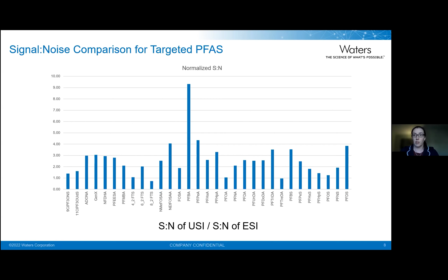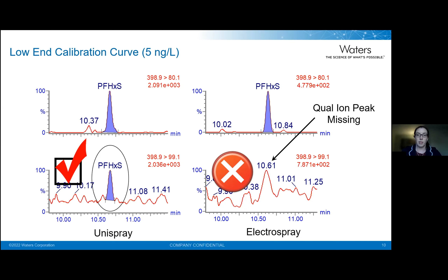So looking at this calibration point for perfluorohexane sulfonate, the Unispray chromatograms are on the left, electrospray is on the right. The top transition is our quantification ion, and the bottom is our qualifier. Usually for us to say that this compound is detected, we need to see traces in both. You can see with the electrospray, we're missing that qualification ion. That qual ion peak is missing, but we do see it in Unispray. So we could call this bottom calibration point an acceptable detection.